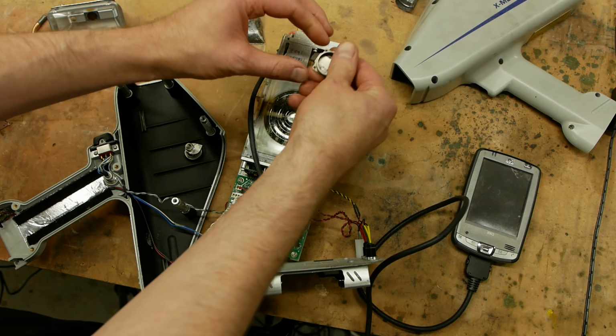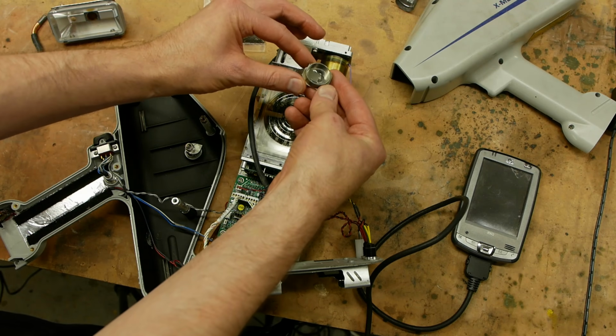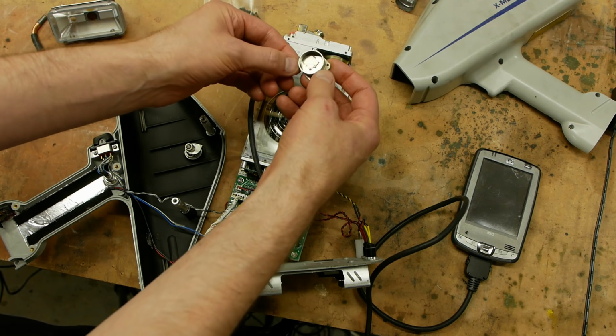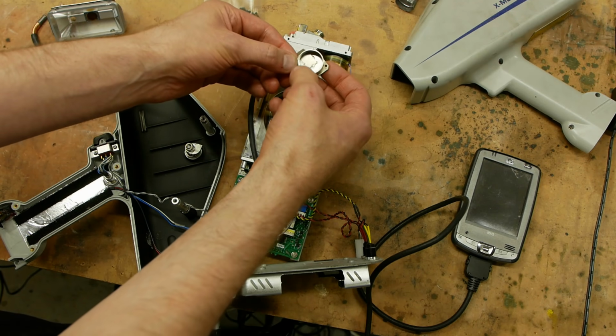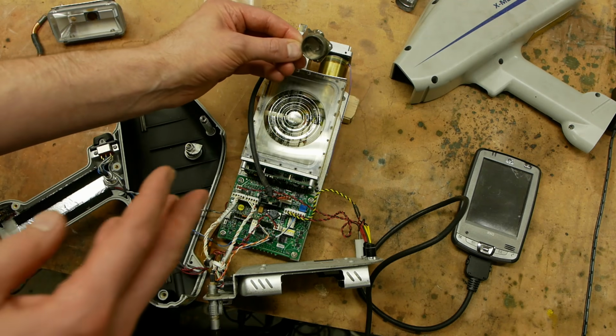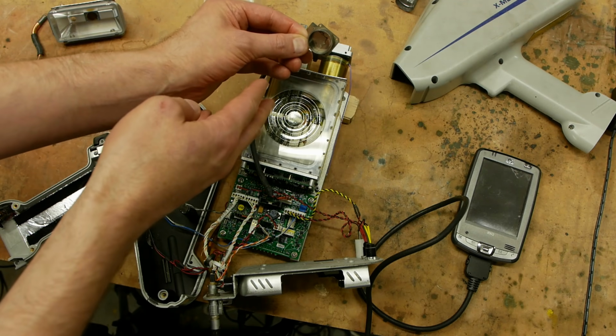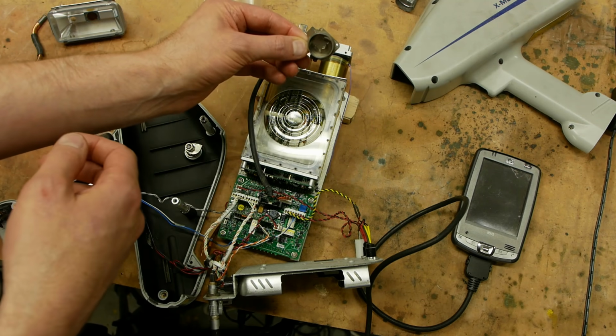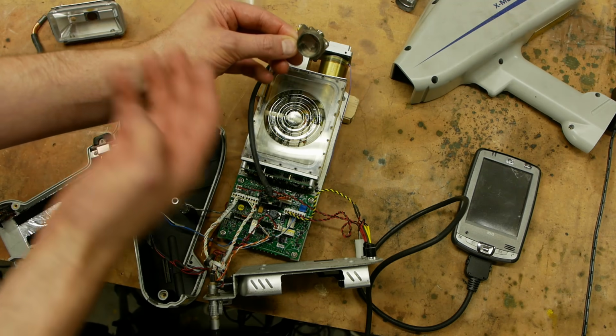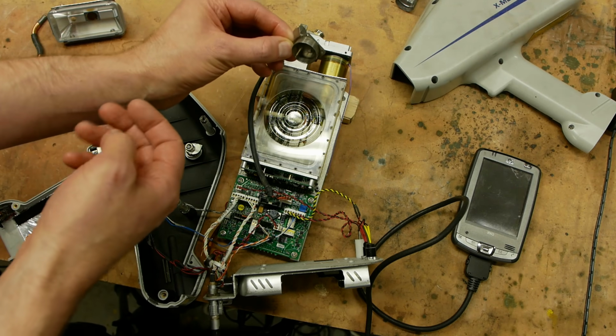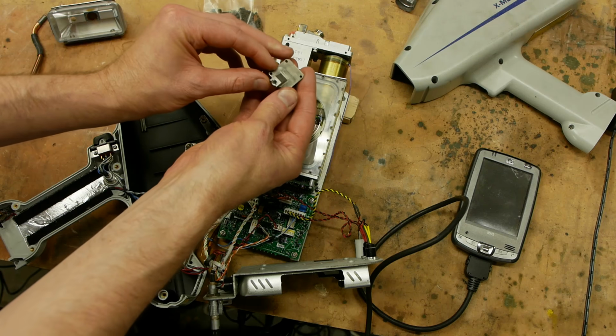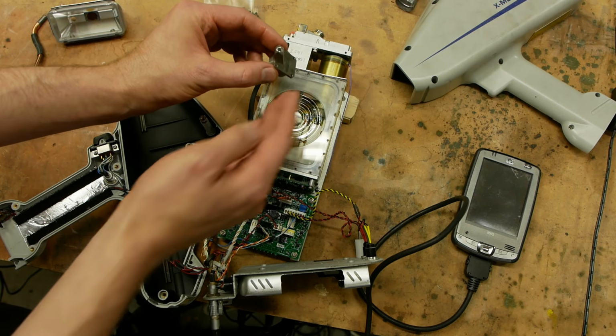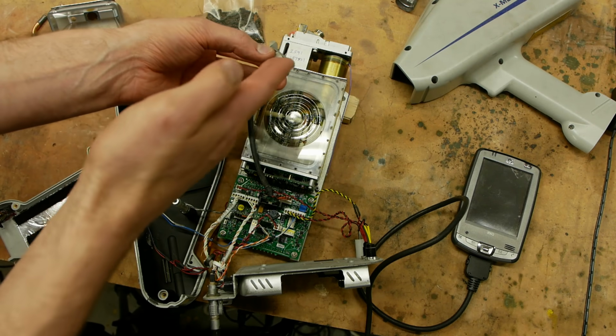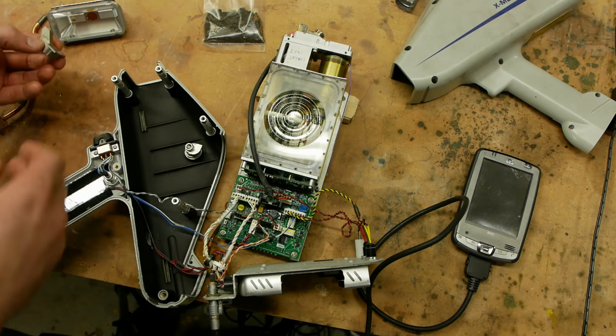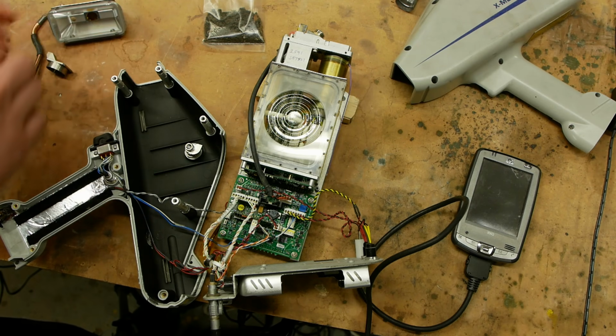And interestingly, inside here there's a little piece of metal. I suspect that that is silver, pure silver metal, that little square of metal that's in there. What happens is the X-rays come in from the tube at various different energy levels, and when they hit the silver it emits a very specific energy level, so that the X-rays that end up coming out of that little aperture there are mostly caused by the silver, the line basically created by silver.